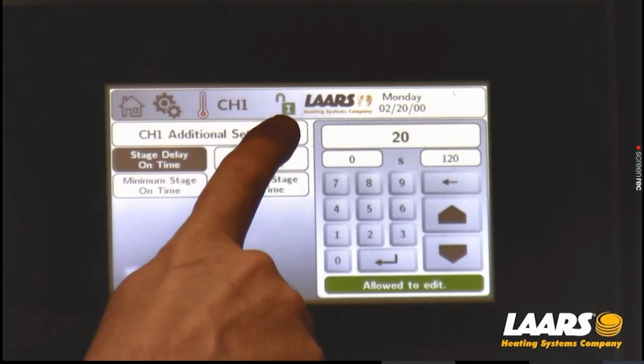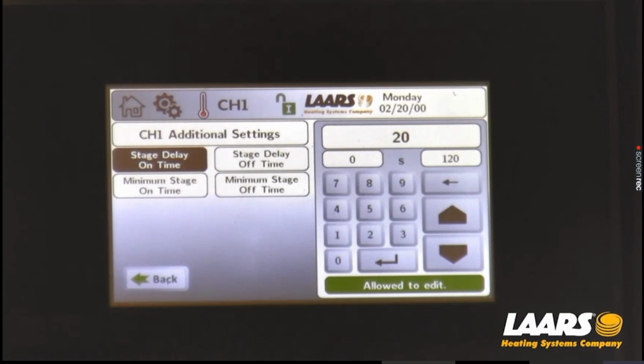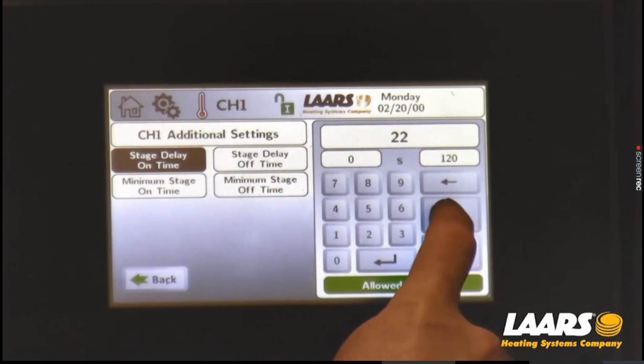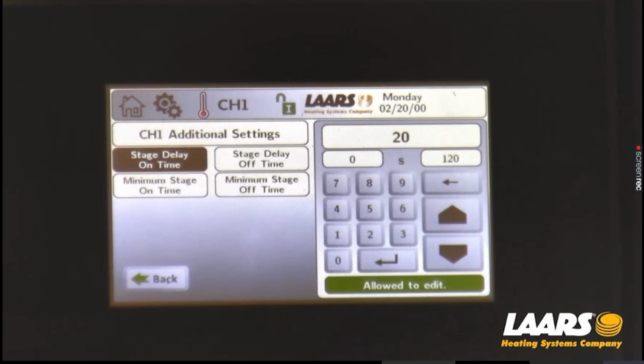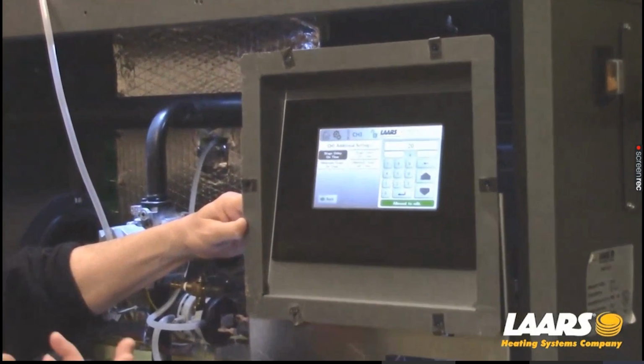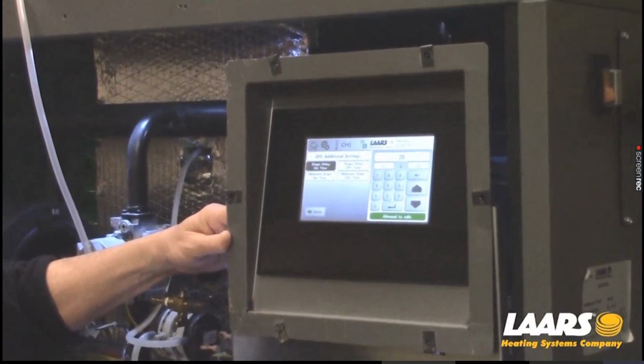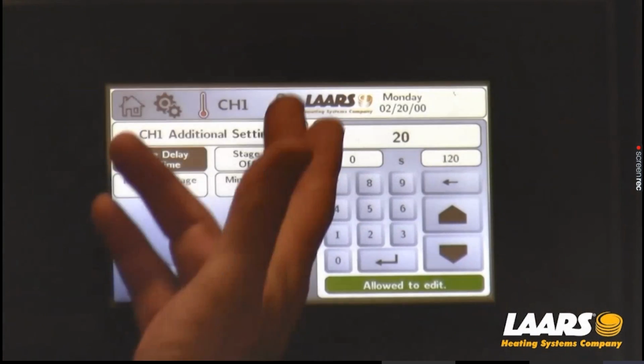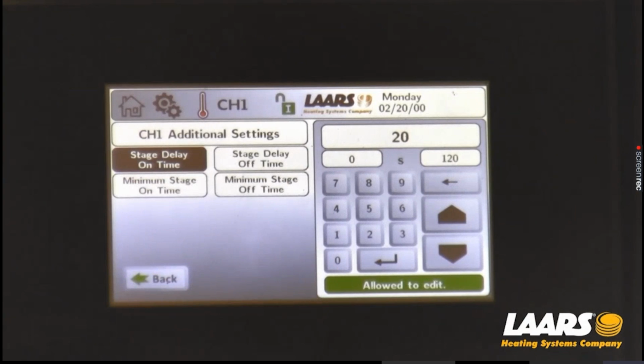I'm in the installer password. If I was not, I can't change it. And again, I drop this down to 20 seconds. You can simply increase or decrease. I would at least give 15 to 20 seconds between stages. Why I'm dropping this down is we don't want to preheat our building loop and take too long. We may not be able to stay in full fire. Combustion testing is only done with all gas valves on. So I've dropped that down to 20 seconds.